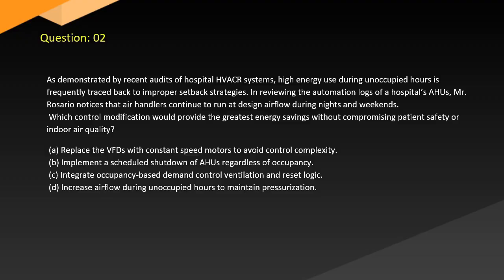Question 2. As demonstrated by recent audits of hospital HVACR systems, high energy use during unoccupied hours is frequently traced back to improper setback strategies. In reviewing the automation logs of a hospital's AHUs, Mr. Rosario notices that air handlers continue to run at design airflow during nights and weekends. Which control modification would provide the greatest energy savings without compromising patient safety or indoor air quality?